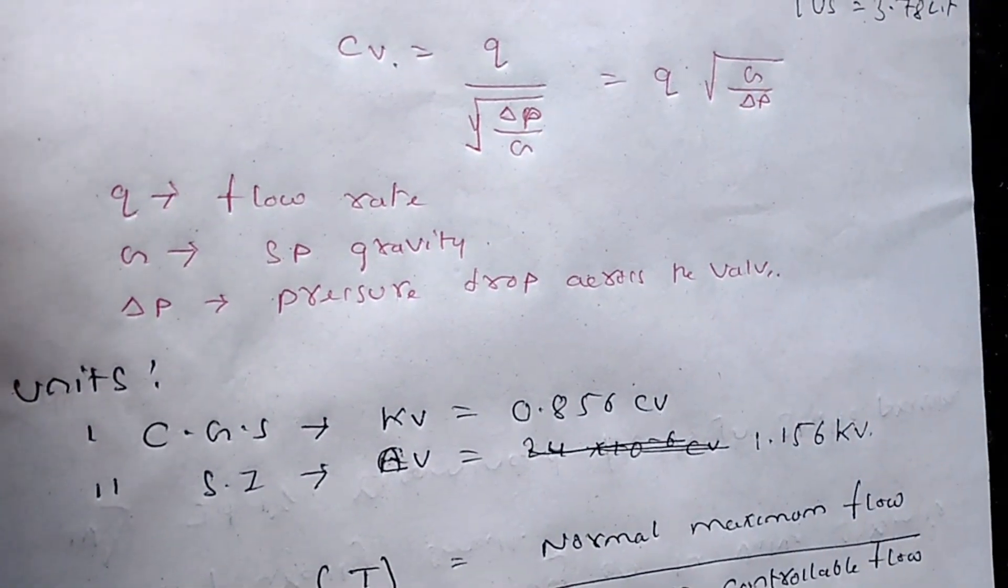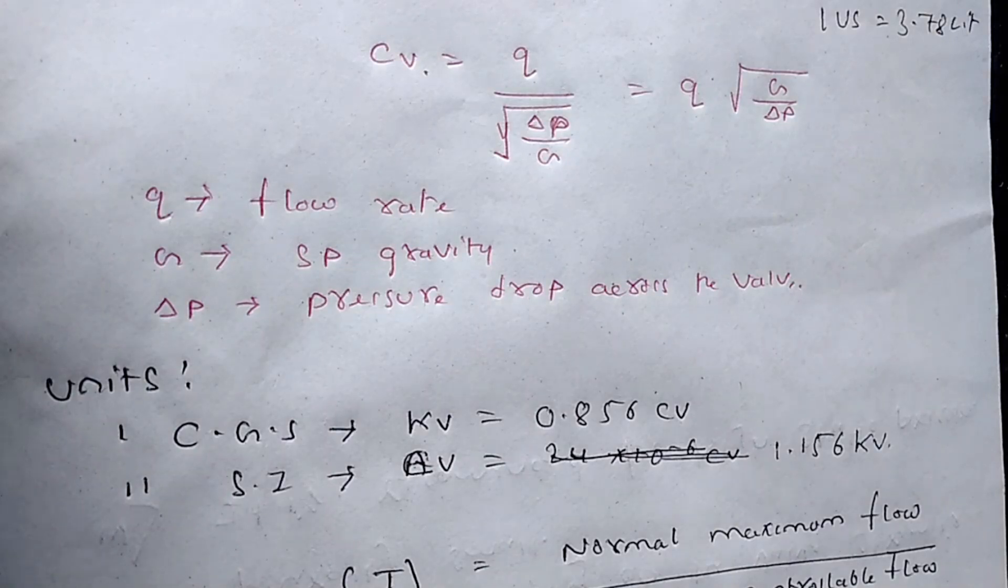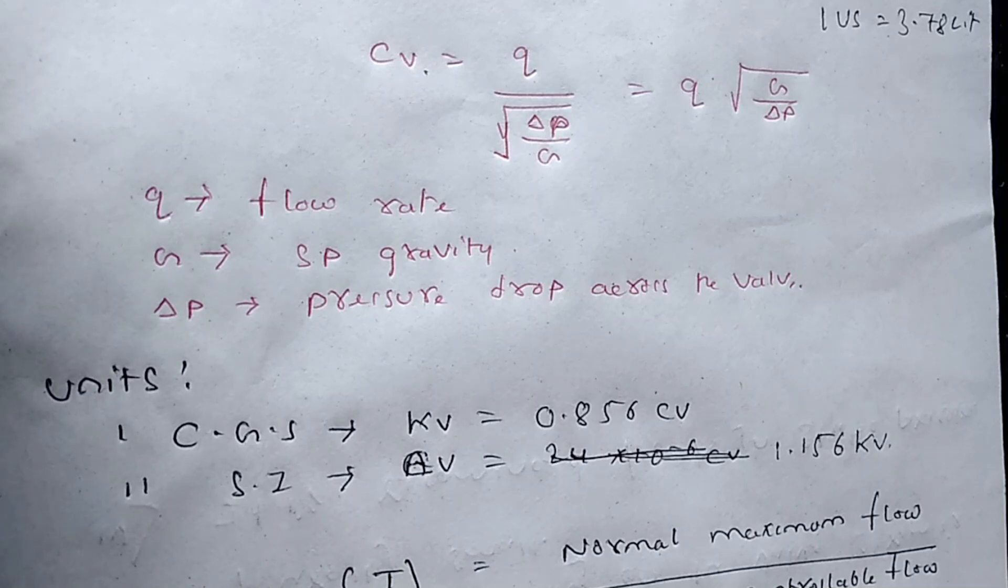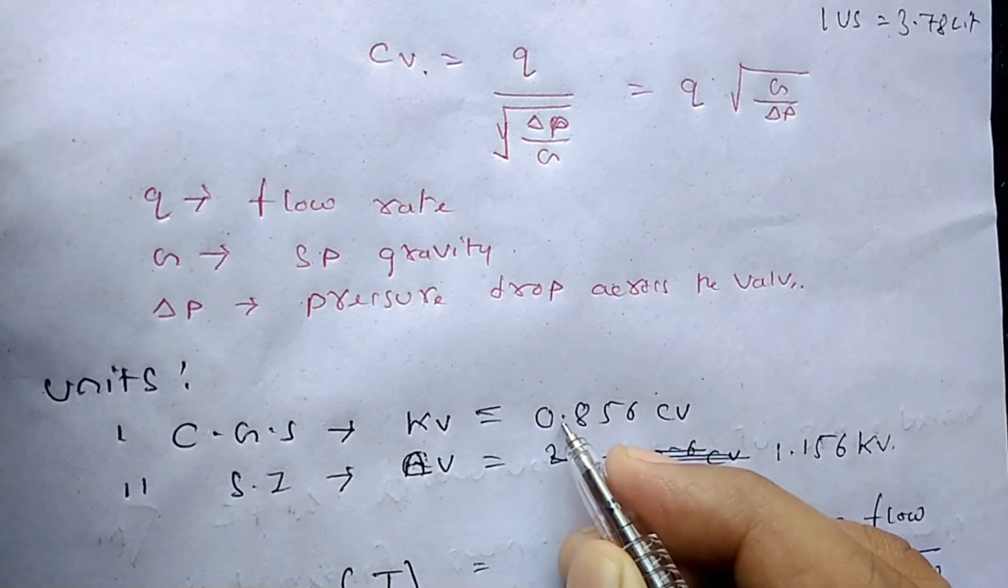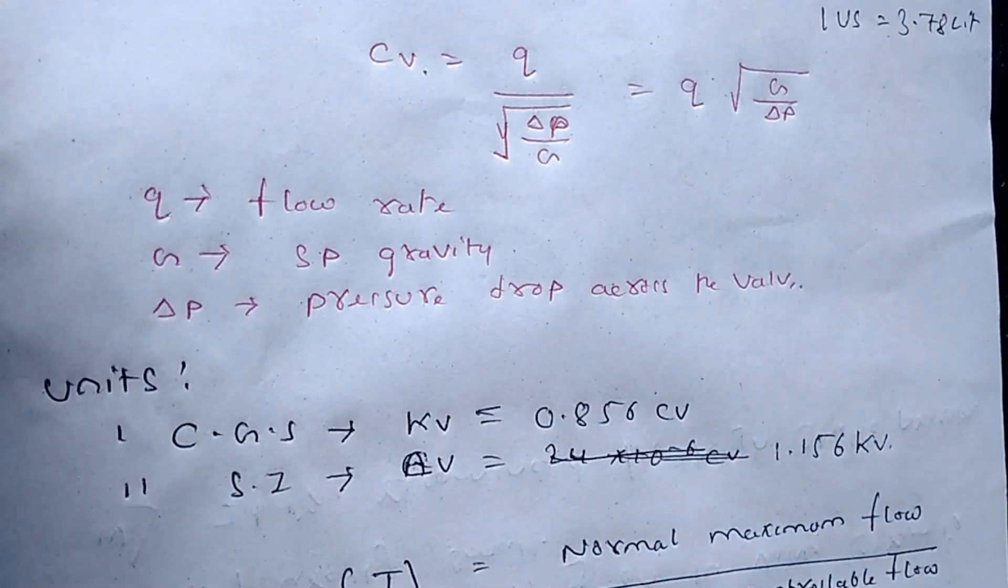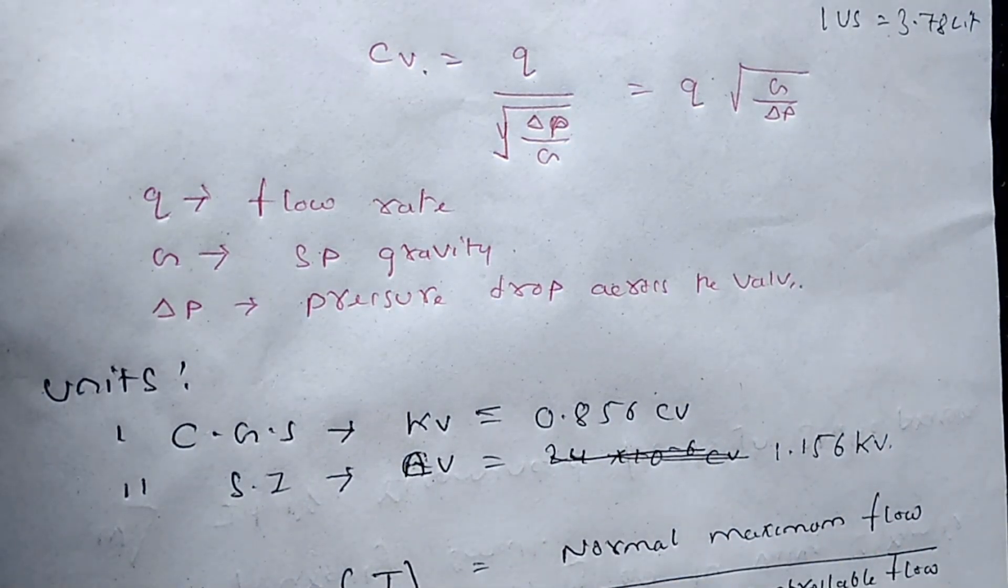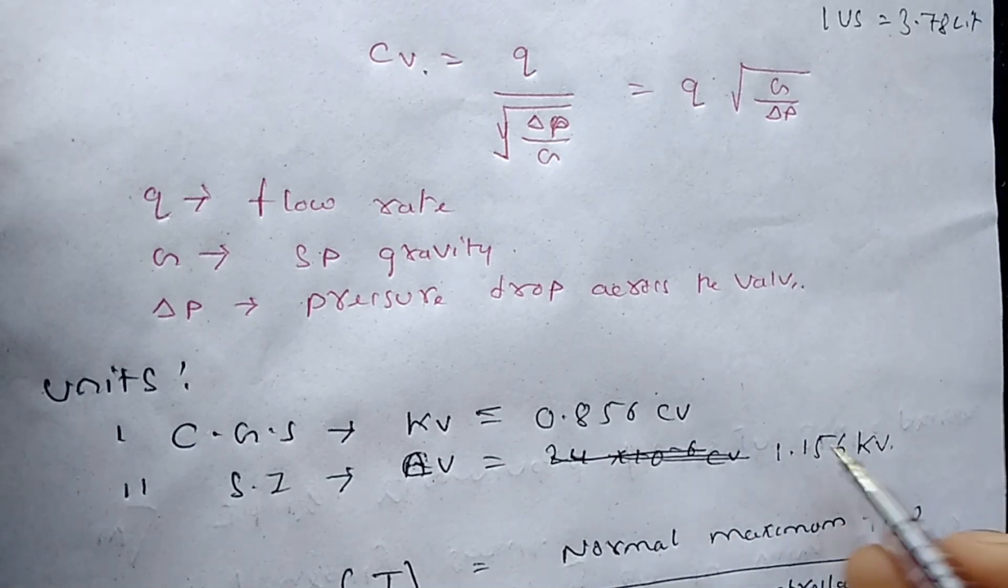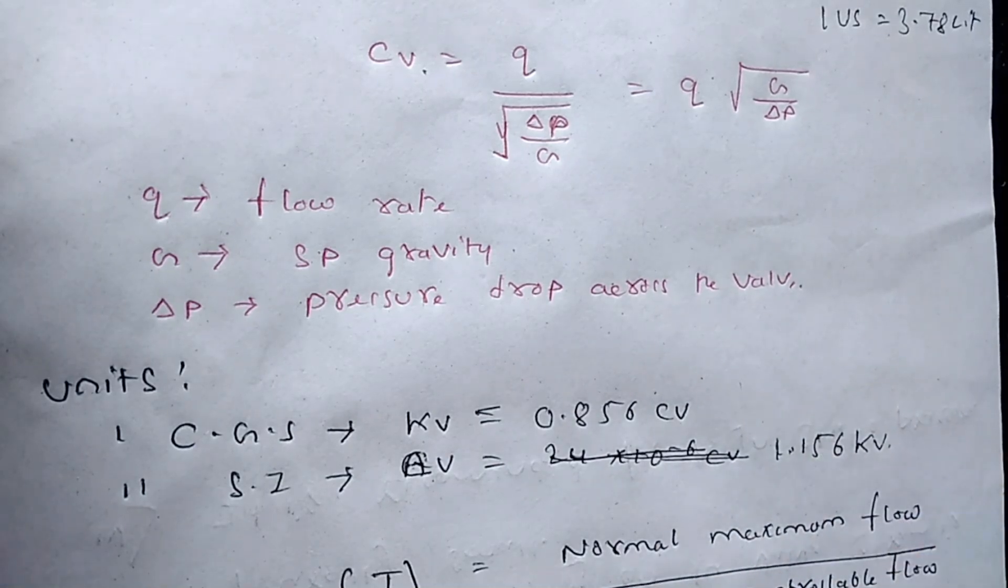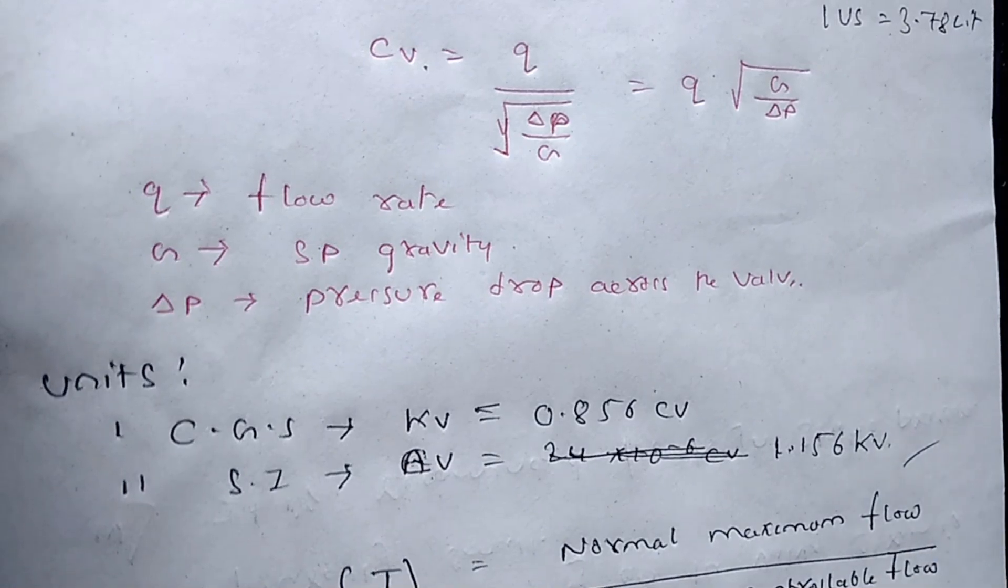Now move to the units. Unit of valve coefficient: In CGS, it is KV. What is KV? The valve coefficient in metric unit. So KV equals 0.856 CV. And in SI, CV, that is coefficient in imperial unit, then 1.156 KV. This point is very important.